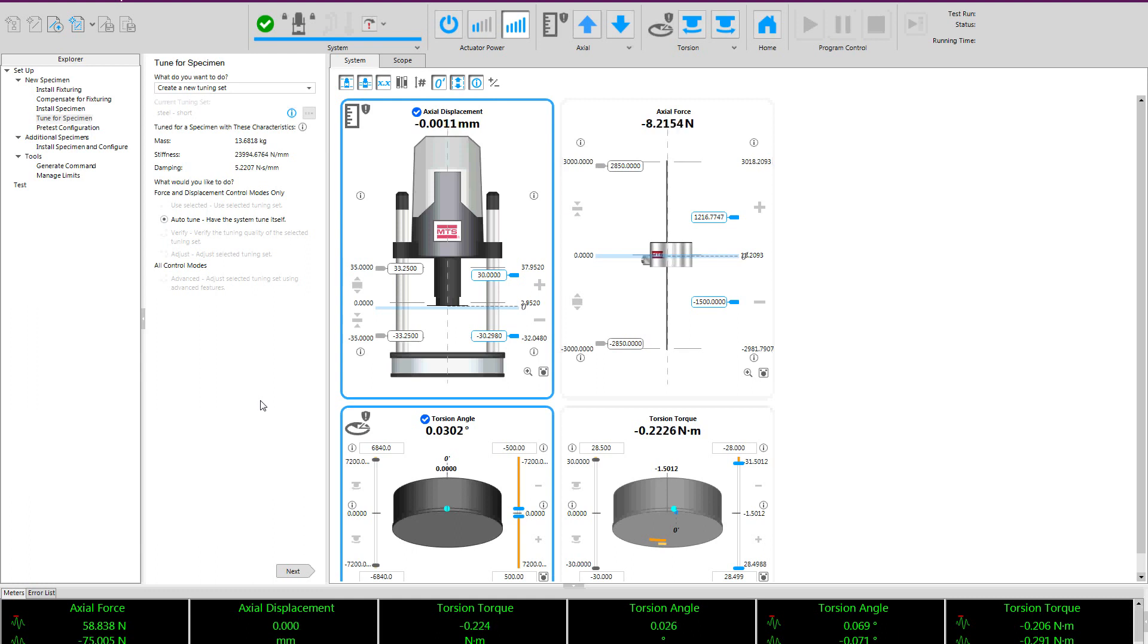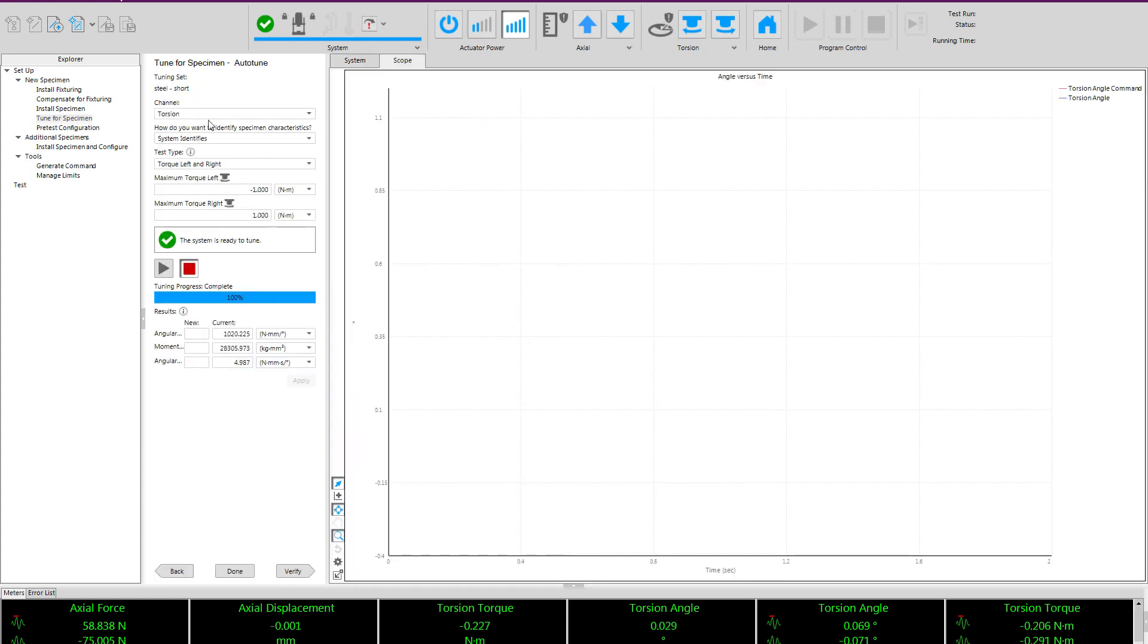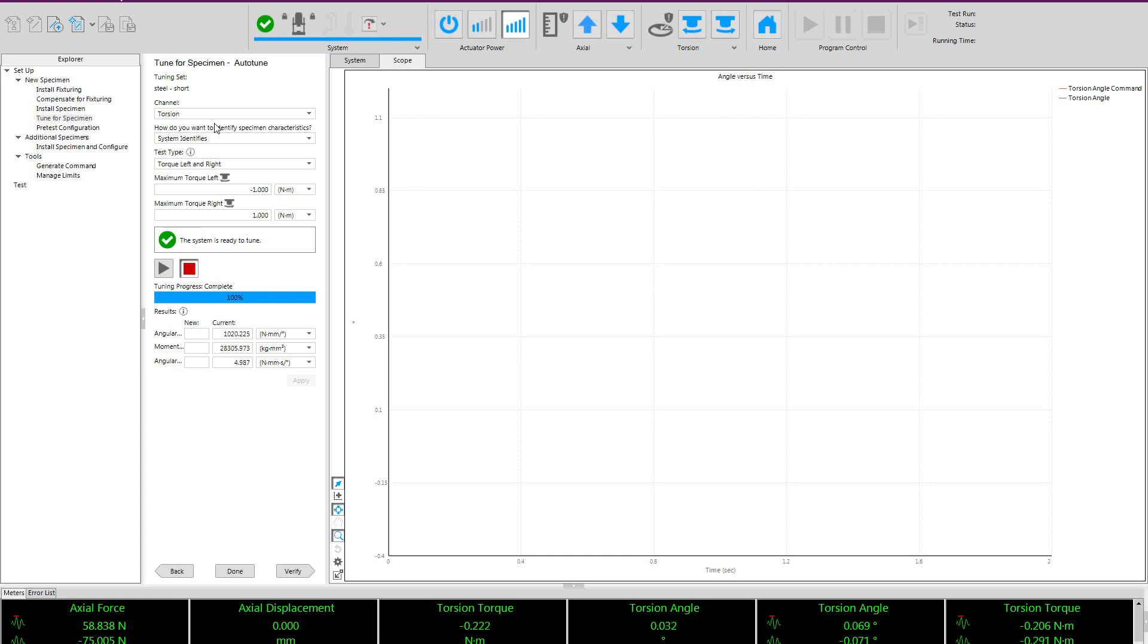You can see here we have our tune for specimen window where we are going to create a new tuning set and we are going to have the system tune itself. We will start with the torsion axis with the system identifying the specimen characteristics. The Acumen auto-tuner functions by measuring all the specimen characteristics: stiffness, mass, and damping to identify the appropriate tuning set.